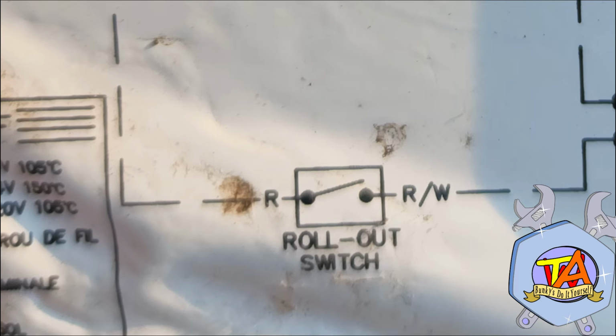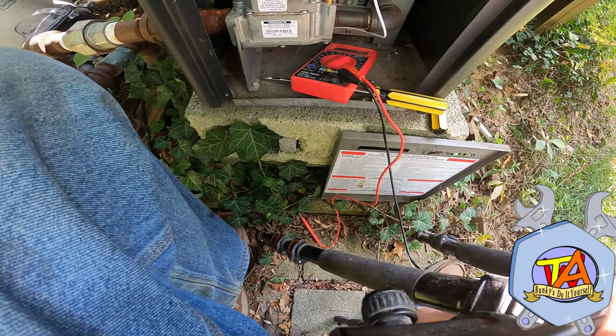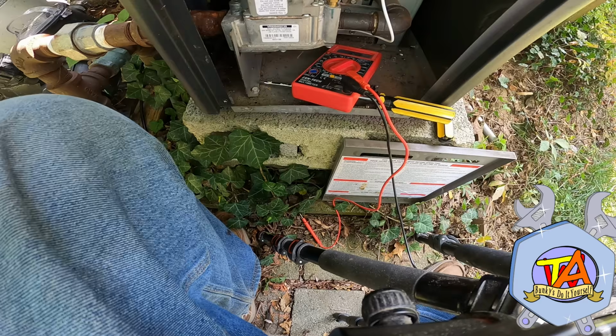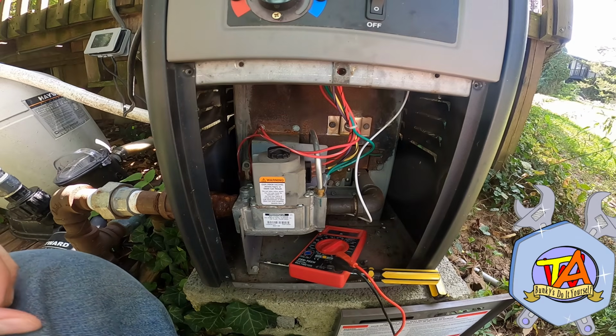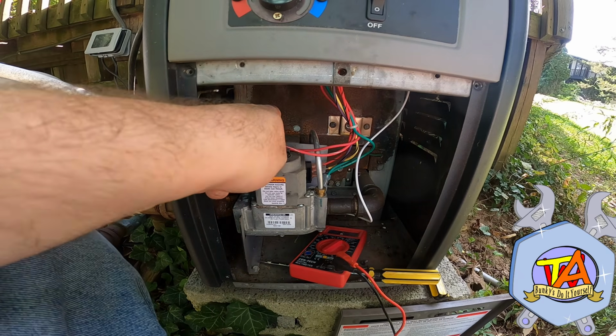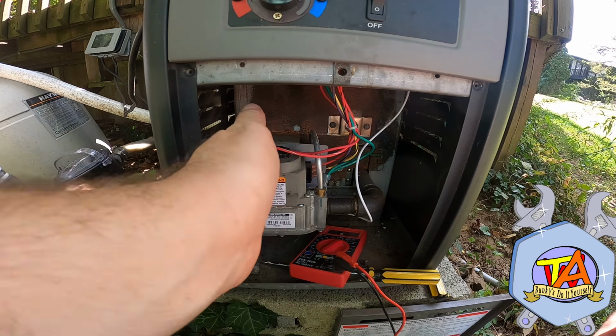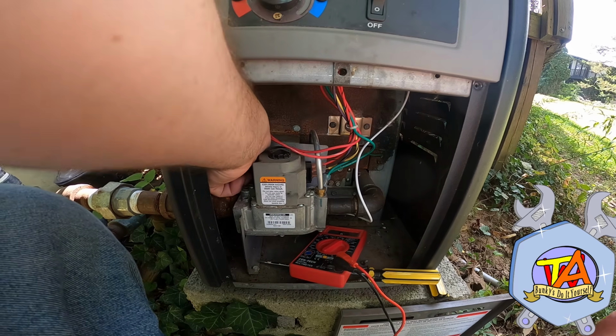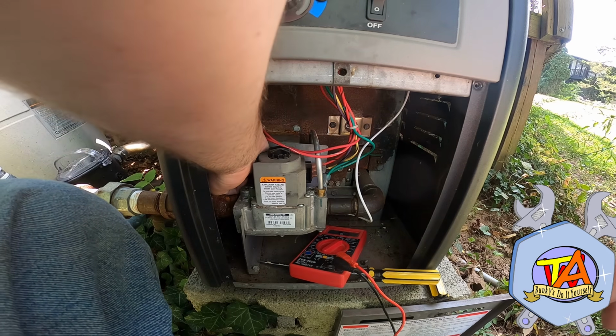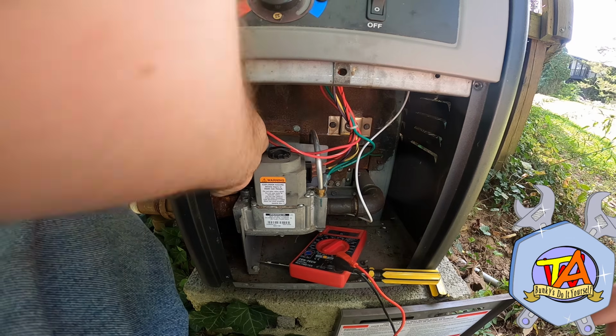The first sensor that I can get to is this rollout sensor. It's a fusible link. It monitors the flame inside the gas heater. If the flame gets hot or creeps back into the unit, the link fuses and shuts down the unit. They can also fuse due to electrical issues. If you have to replace this multiple times, there might be something wrong with the electrical system. So you want to go ahead and check all of the wires, making sure that there's no loose wires, and make sure everything's well grounded.